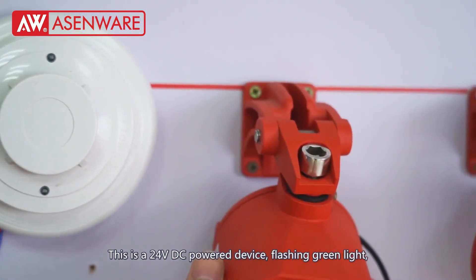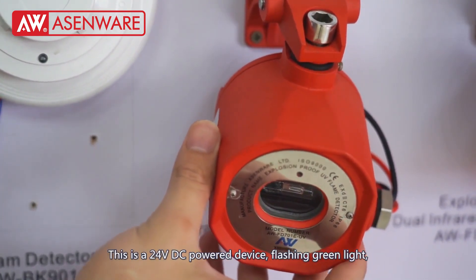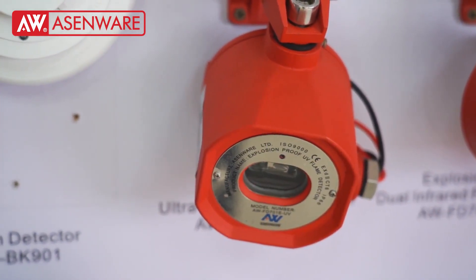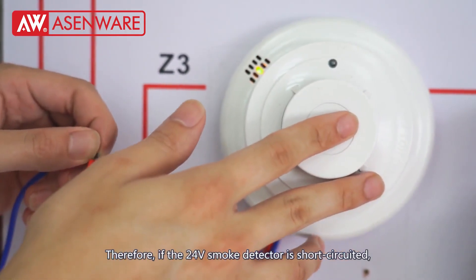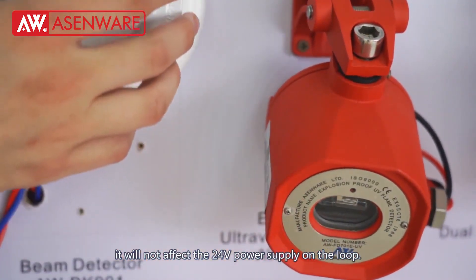This is a 24V DC powered device, flashing green light, meaning that it is still in normal working state. Therefore, if the 24V smoke detector is short circuit, it will not affect the 24V power supply on the loop.